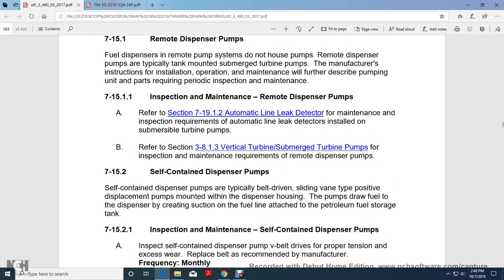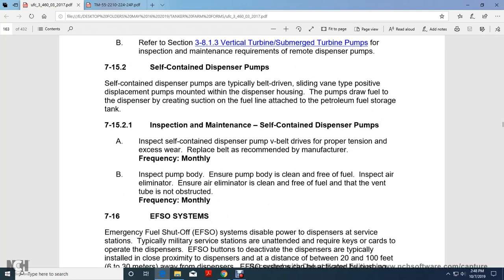Inspection maintenance of remote dispenser pumps. Refer to Section 79121, automatic line leak detector, for the maintenance requirements of the automatic line leak detectors installed on the submersible turbine pumps. Refer to Section 3813, vertical submerged turbine pumps, for inspection maintenance requirements of remote dispenser pumps. 715.2 self-contained dispenser pumps. Self-contained dispenser pumps are typically belt driven sliding vane, of the positive displacement type, mounted on the dispenser housing. The pump draws fuel to the dispenser, creating suction with the fuel line attached to the petroleum fuel storage tank.